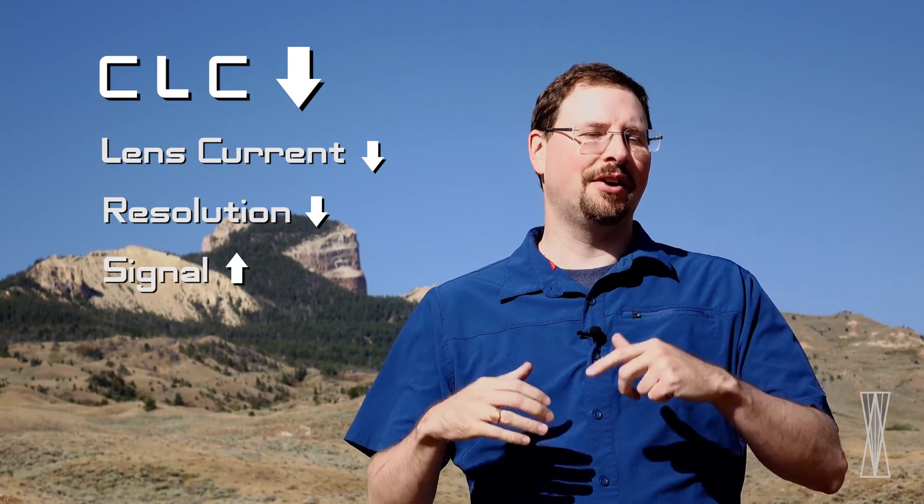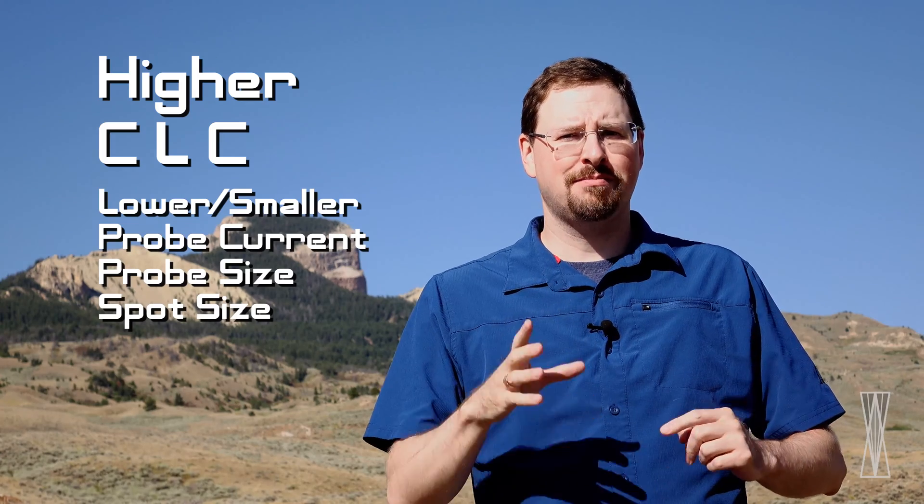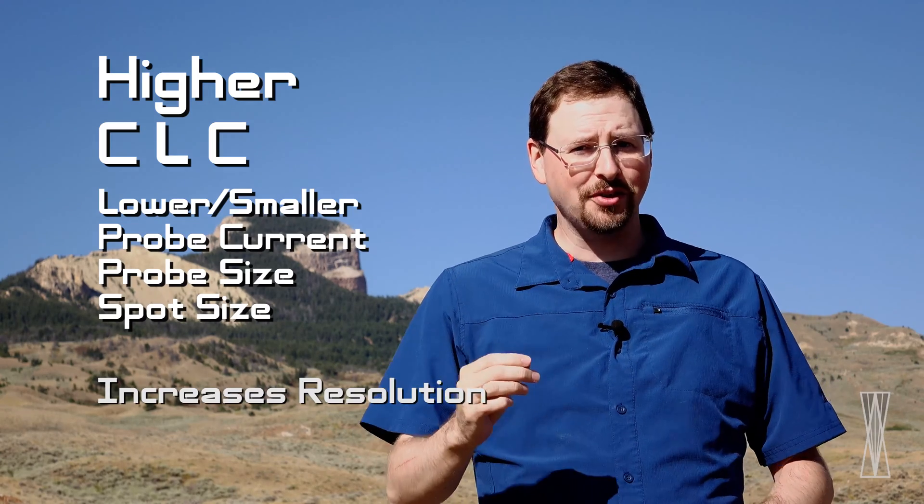Turning it down meant the lens current went down, the resolution went down, and the signal went up. Nowadays, most microscope manufacturers will label this control not as CLC but as spot size, probe size, or probe current. This label is the inverse, or opposite, of the condenser lens current. A control that says condenser lens current tells you what you're changing; a control that says probe current or spot size tells you the result you get from changing that control. For example, turning down the condenser lens current allows more electrons down the column, giving you a larger probe current or larger spot size. So to recap: a higher condenser lens current, which is a lower or smaller probe current, probe size, or spot size, will give you better resolution but lower signal.